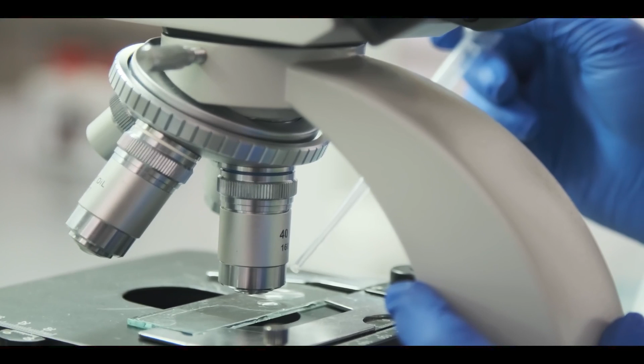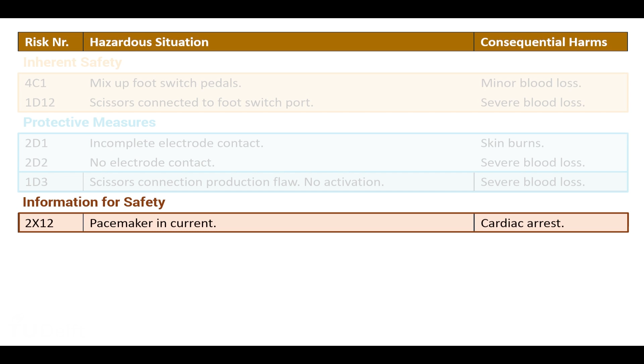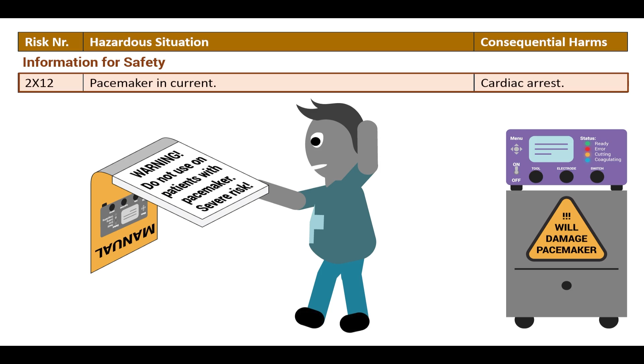And the last risk that we will tackle for now is the situation of accidentally having a patient's pacemaker in the current flow towards the return electrode. The potential harm is quite serious, but there doesn't seem to be anything obvious we could do to make the system inherently safe. In this case, we chose to reduce the probability of this situation occurring by relying on the trained clinical professionals, by training them for using this device and putting warning signs in the user manuals and on the device to alert the users. But of course, this will only work if the user pays attention.